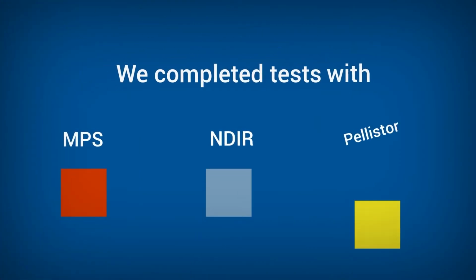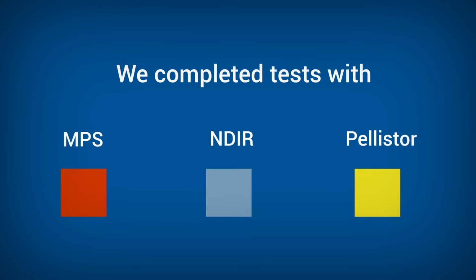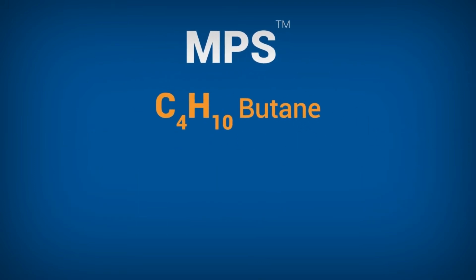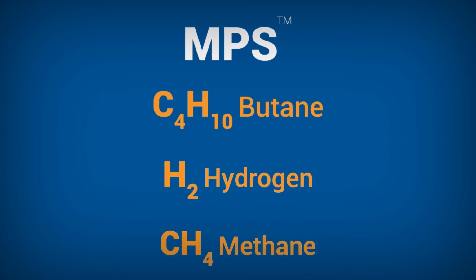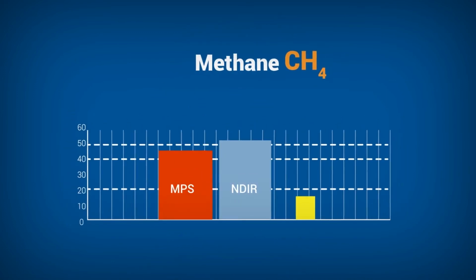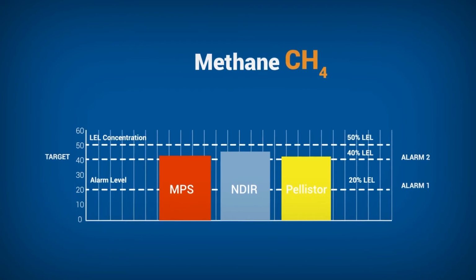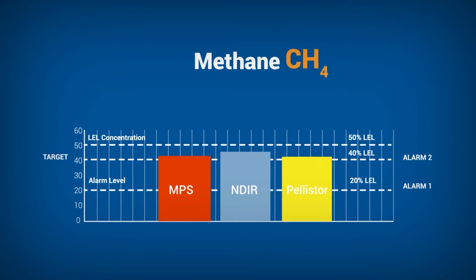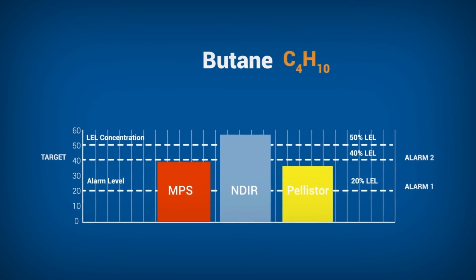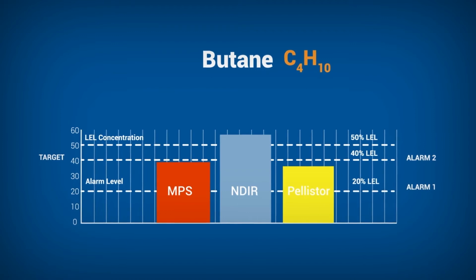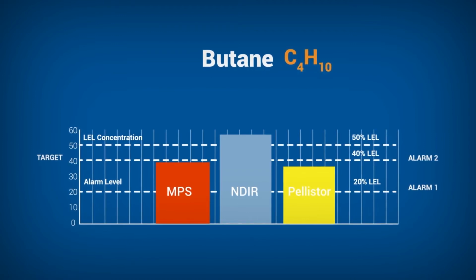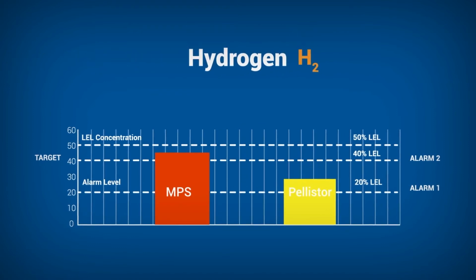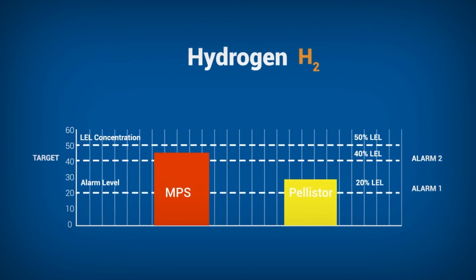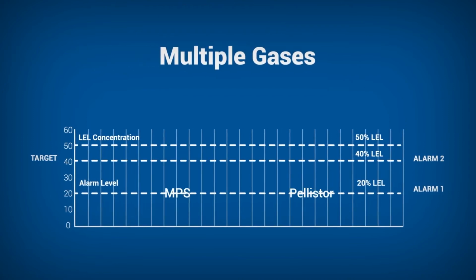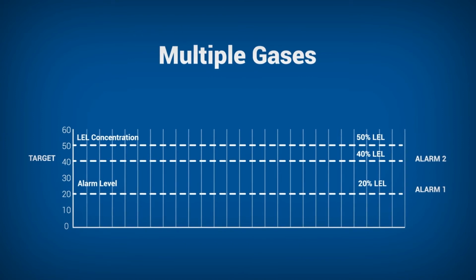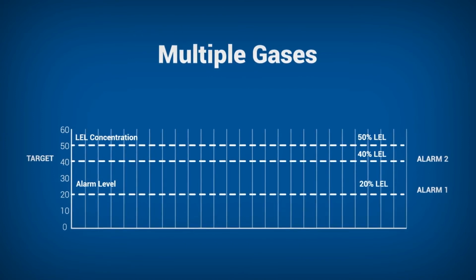Additionally, we completed live tests and exposed the MPS, NDIR, and Pellistor to butane, hydrogen, and methane released into an environment at 50% LEL. The first test with methane resulted in all sensors accurately measuring the gas and reaching both alarm levels. But when we tested butane, all sensors detected some level of the gas, but only the MPS sensor provided an accurate reading. With hydrogen, the Pellistor underdetected the gas, resulting in a potentially dangerous masked alarm. The NDIR showed no detection, missing all alarms. Only the MPS provided accurate detection.